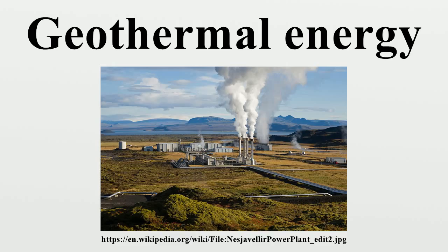Pumps are generally not required, powered instead when the water turns to steam. Most wells generate 2 to 10 MWe. Steam is separated from liquid via cyclone separators, while the liquid is returned to the reservoir for reheating and reuse. As of 2013, the largest liquid system is Cerro Prieto in Mexico, which generates 750 MWe from temperatures reaching 350 degrees Celsius. The Salton Sea field in Southern California offers the potential of generating 2,000 MWe.